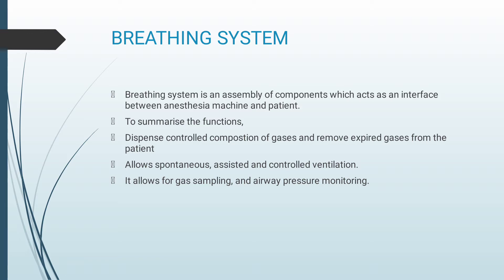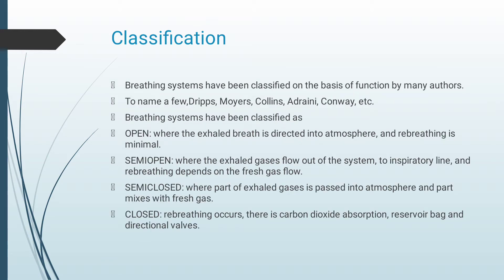Moving on to breathing systems. The breathing system is an assembly of components which acts as an interface between the anesthesia machine and patient. It dispenses controlled composition of gases, removes expired gases from the patient, allows spontaneous, assisted, and controlled ventilation, and allows for gas sampling and airway pressure monitoring. Breathing systems have been classified by many authors — DRIPS, Moyers, Collins, Conway — as open, semi-open, semi-closed, and closed.